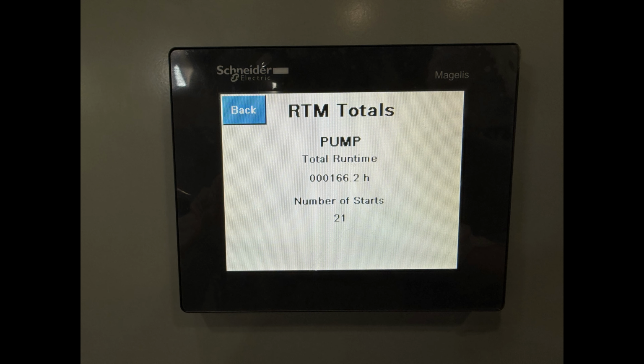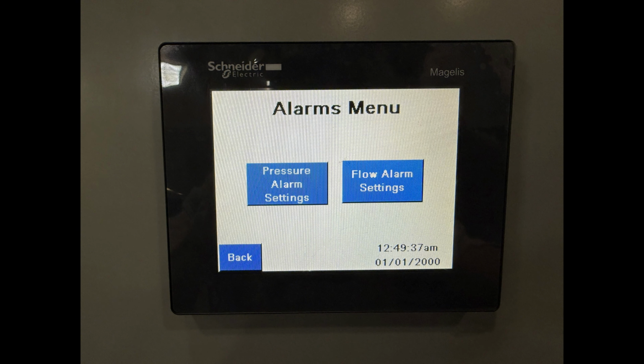Moving on, we can see our runtime totals. Again, our pump has ran for 166.2 hours, and we have had 21 number of starts. We can go to our alarms menu, and we can see our pressure alarm settings and our flow alarm settings.